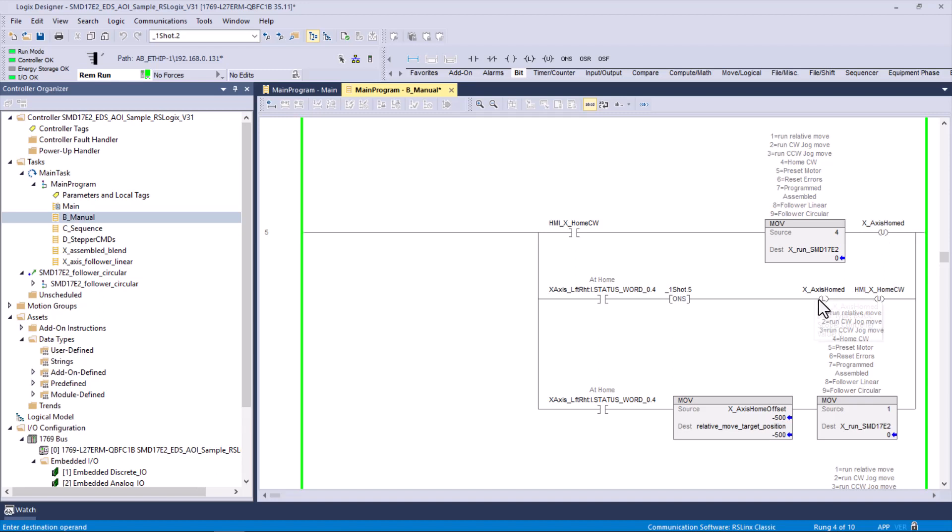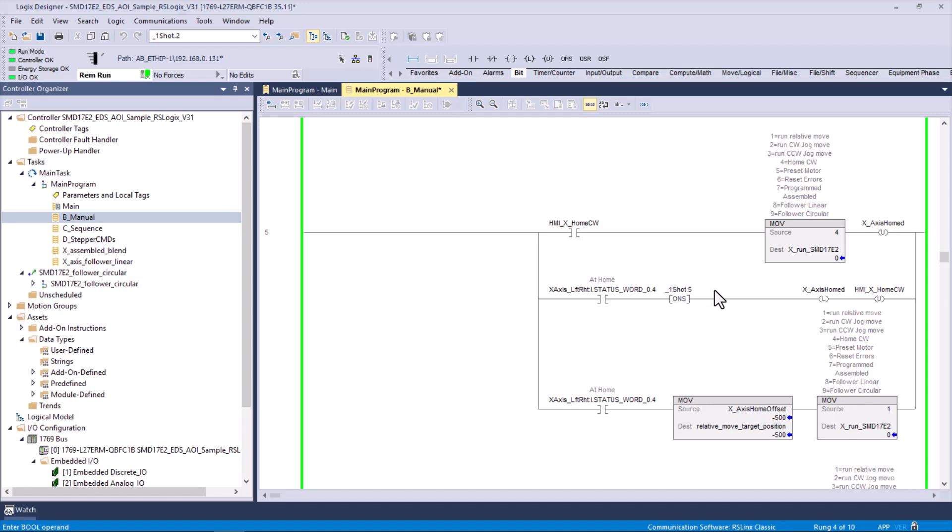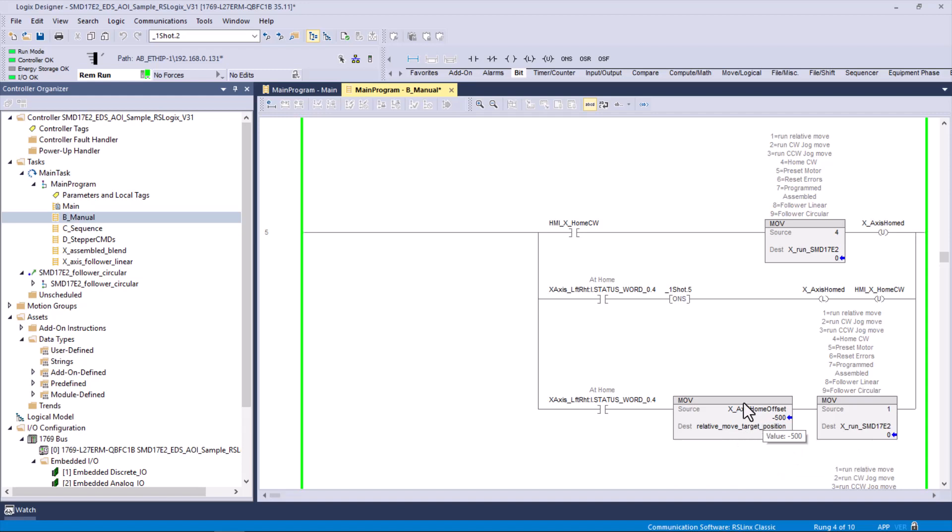If this has already been homed, I latched on this bit right here, x-axis homed. I'm not sure whether I'm going to use that or not. I would like to have a bit that says it was homed because this bit, bit four of this status word, is only true when it is at home. We're using when it reaches home to one shot, latch that it's been homed, then unlatch our HMI button. When it's at home, I put in an offset, a value, and keep in mind because of the way this thing is built, the clockwise and counterclockwise rotation, I'm moving in a negative direction from home.